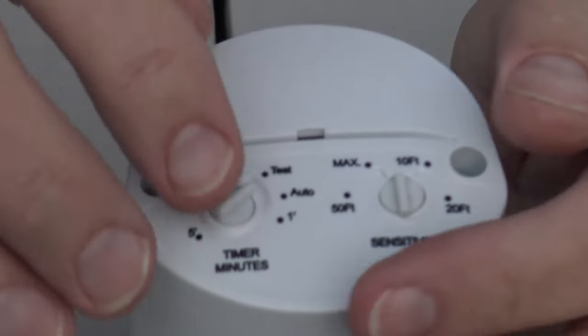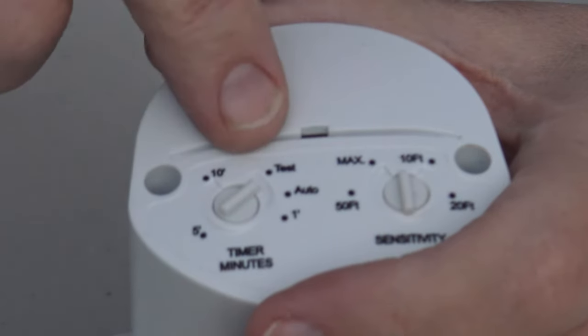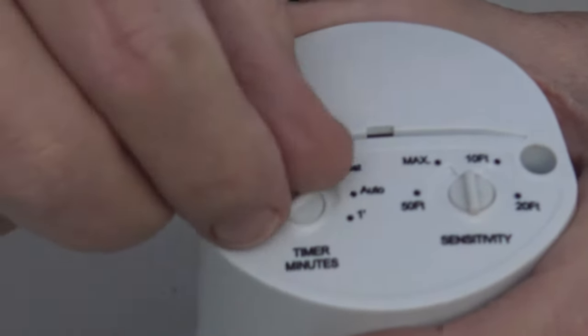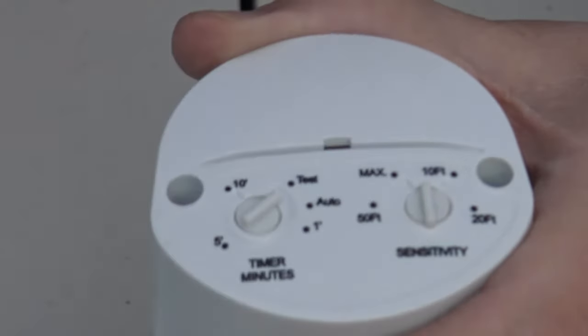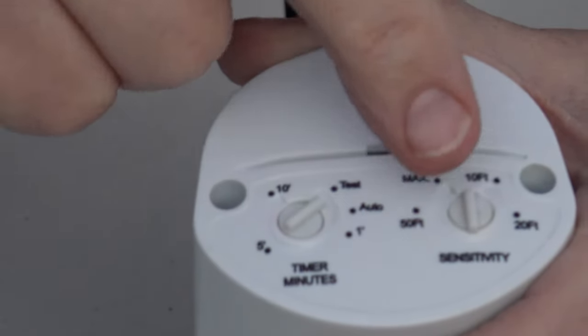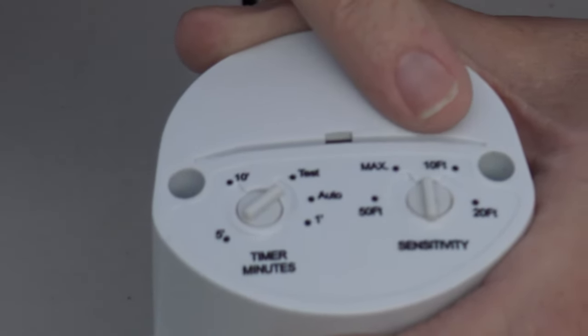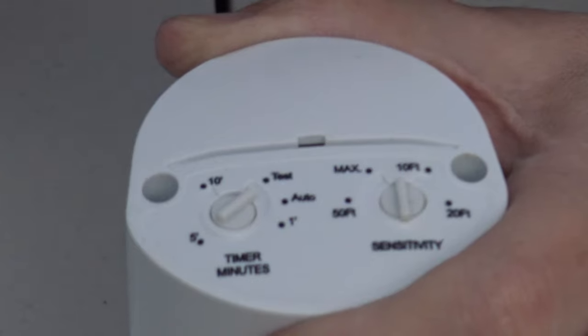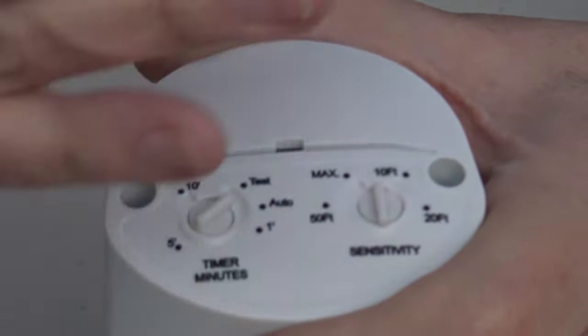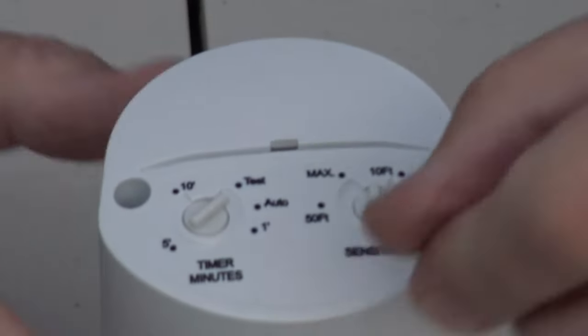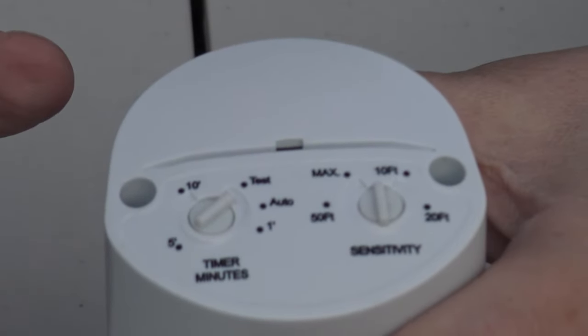Take the controls, set your minutes dial to test, which is right there. Now there's a stop right there, so you can't go any further. Set it to test. And what I typically do is I set the sensitivity, which is the distance to the middle point, which is about 30 feet. You can always adjust that later.